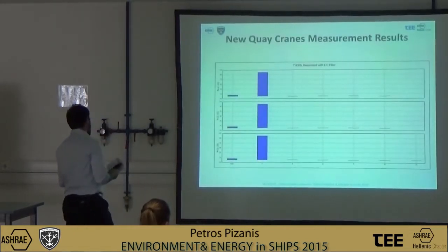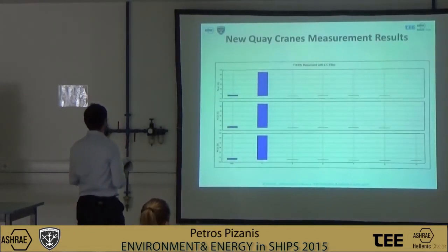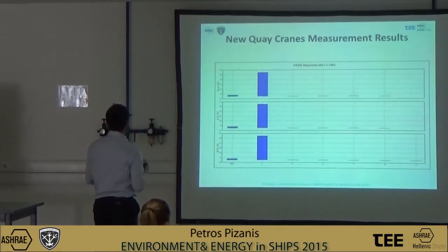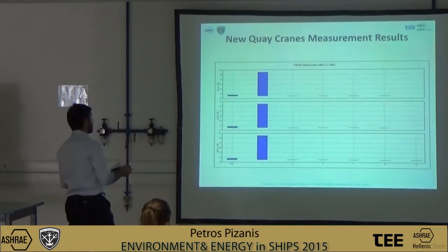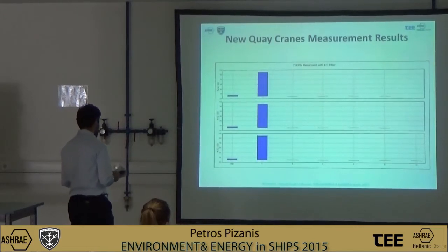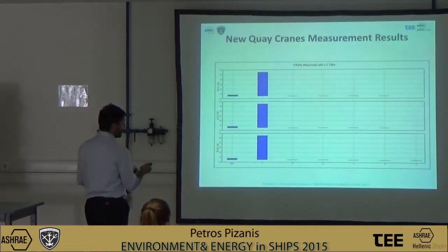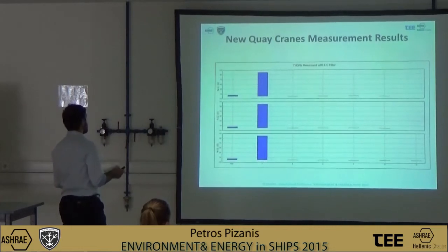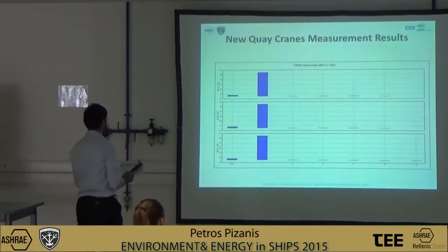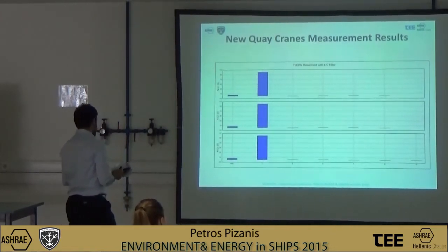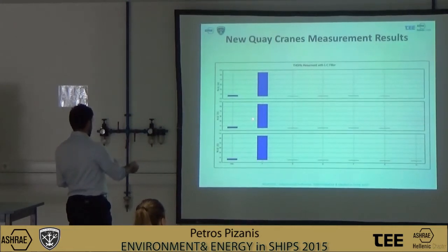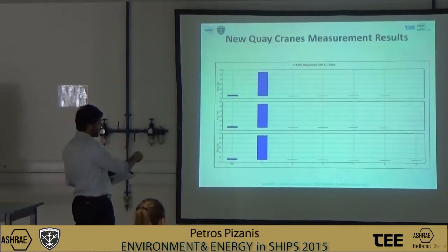Now, from the other side, we can see a crane with newer technology, which does have filters and also a system to regenerate return voltage during motor braking, thus making the crane more environmentally friendly and also acceptable. And as you can see, there are no harmonics, it is almost 0%. And the first one, of course, is not a harmonic. This is our fundamental frequency at 50 Hz.